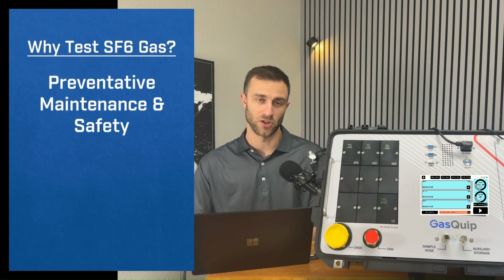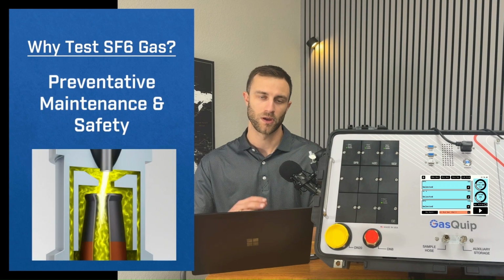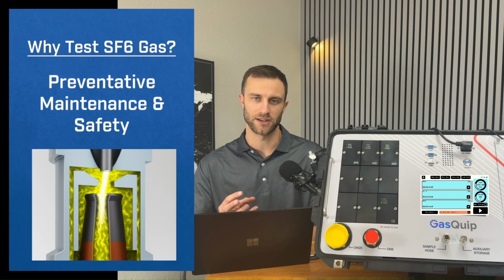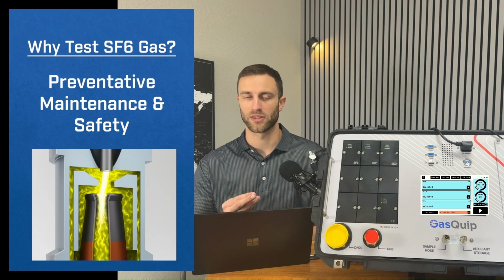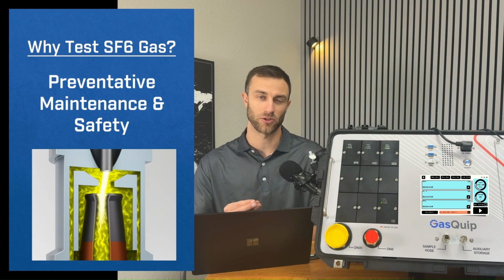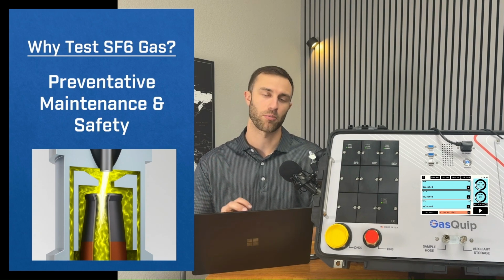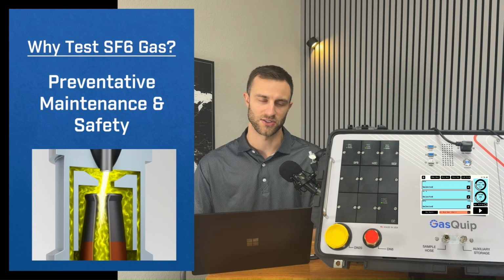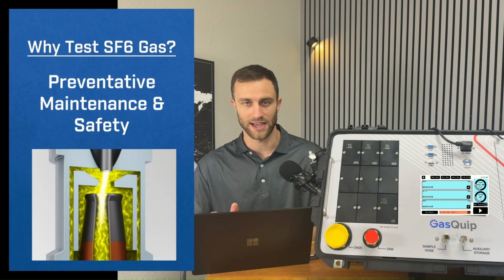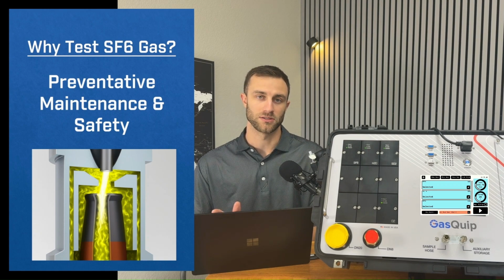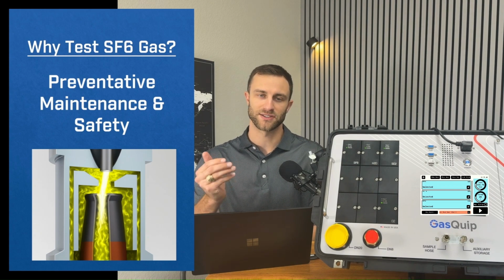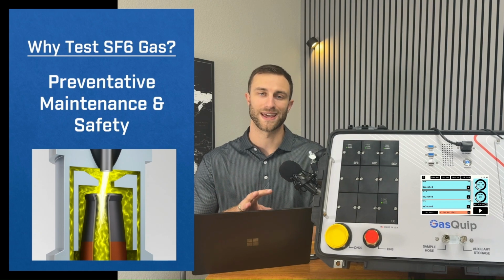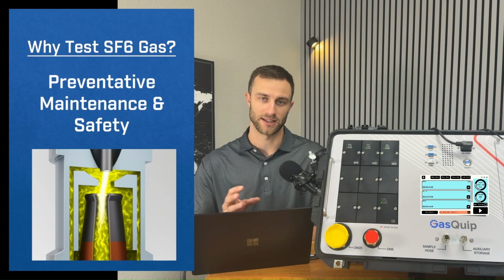And the other thing is safety. So on the internals of this breaker that's shown here, there's a lot of heat generated, and that heat, whenever it's mixed with SF6 and moisture and other contaminants, it can create a petri dish of other arc byproducts that can be produced by the system. So for the operator that's testing the gas, we need to be aware that there are types of arc byproducts that can be produced that are very harmful and toxic to operators and should not be breathed in. And so if you're testing the gas, that'll give you a good picture of what the gas actually is made up of and whether or not it's safe to handle if you're pulling the gas in and out of the breaker.